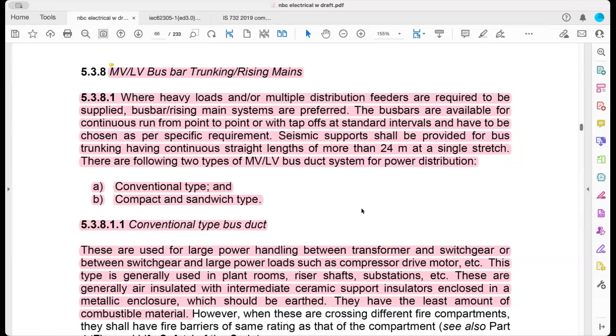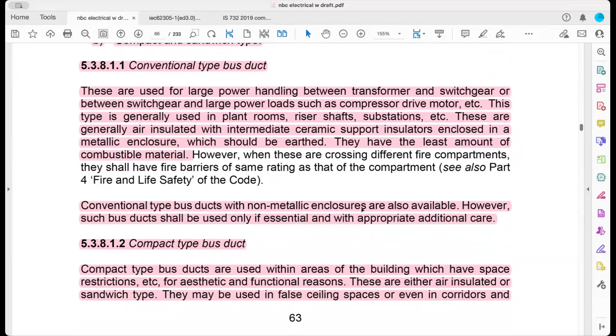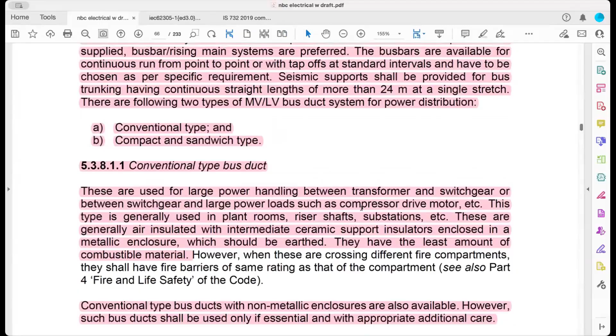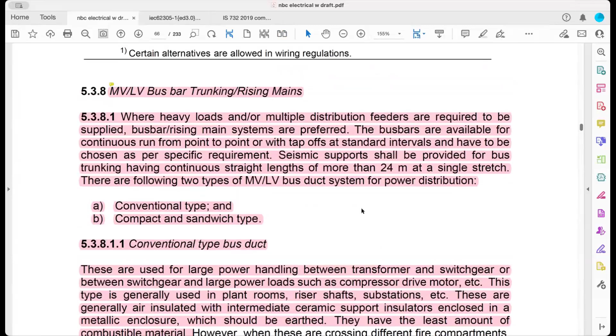Well, unfortunately, there's not much I can explain because, as you correctly mentioned, IEC 61439 Part 6 doesn't use these terms: conventional type, compact and sandwich type. In fact, bus duct is a term used in NBC, which is not used in IEC. It is busbar trunking system. Frankly, I don't see what requirement this particular section gives for an installation standard at all, other than something to do with spacing.